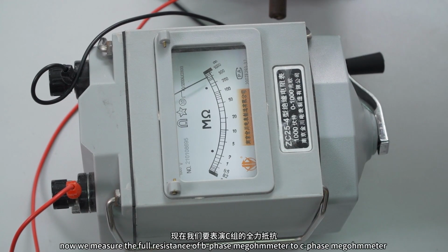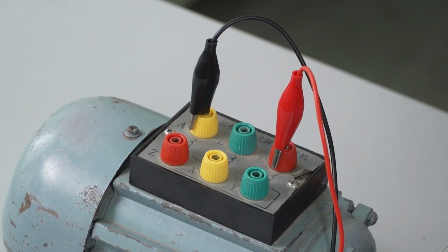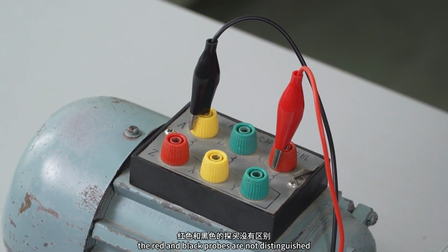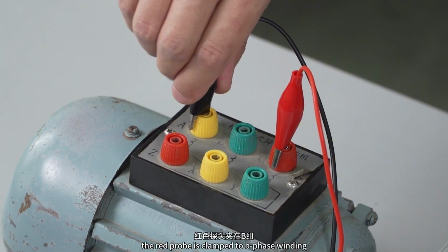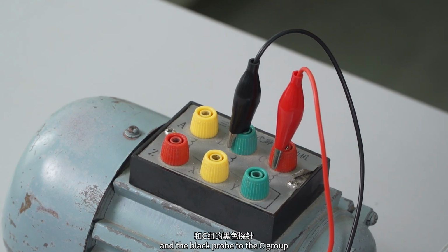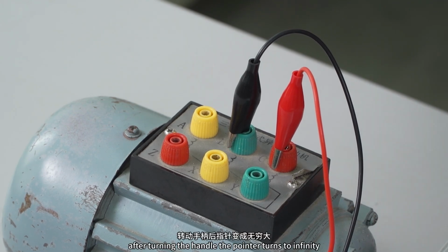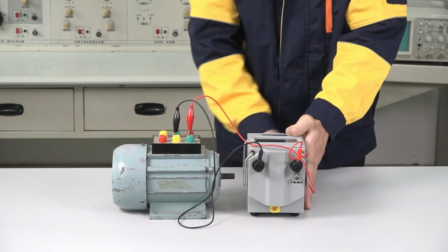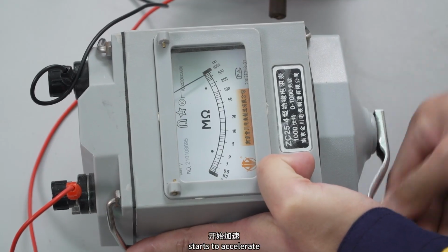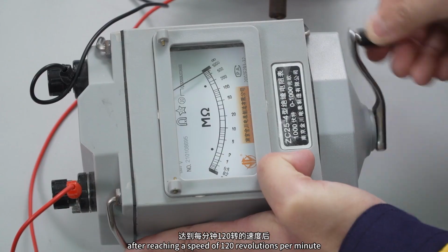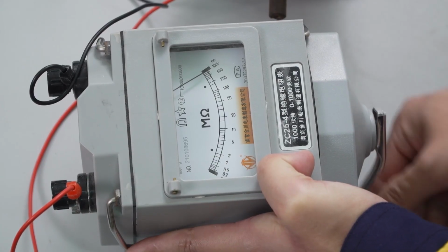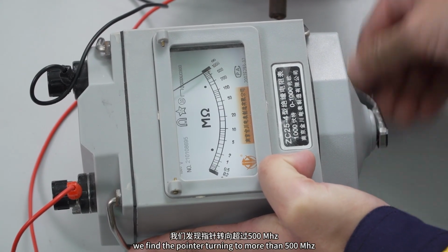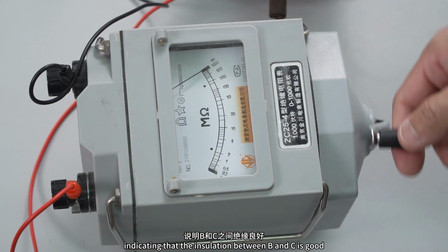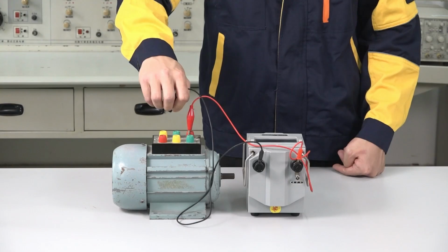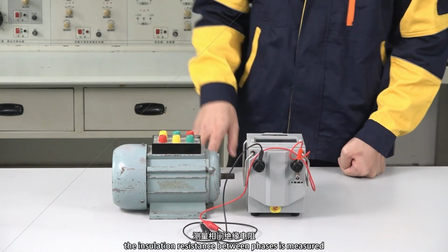Slowly stop. Now we measure the insulation resistance of the B phase winding to the C phase winding. When measuring, the red and black probes are not distinguished. The red probe is clamped to the B phase winding, and the black probe to the C phase winding. After turning the handle, the pointer turns to infinity. Starts to accelerate. After reaching a speed of 120 revolutions per minute, we find the pointer turning to more than 500 megohms, indicating that the insulation between B and C is good. Slowly stop. The insulation resistance between phases is measured.